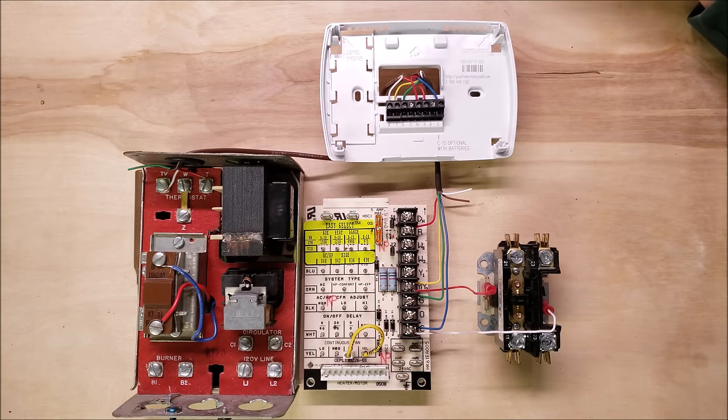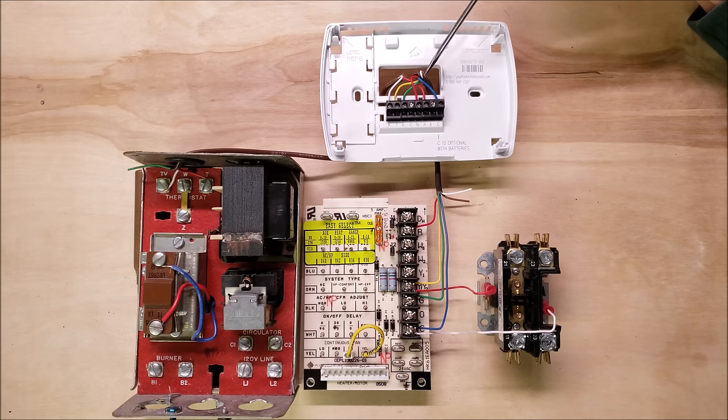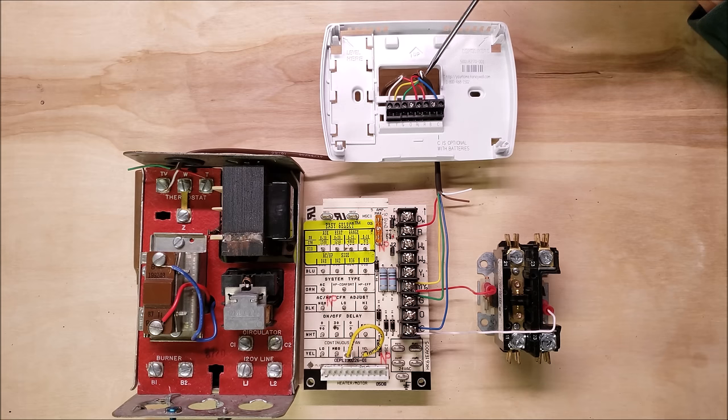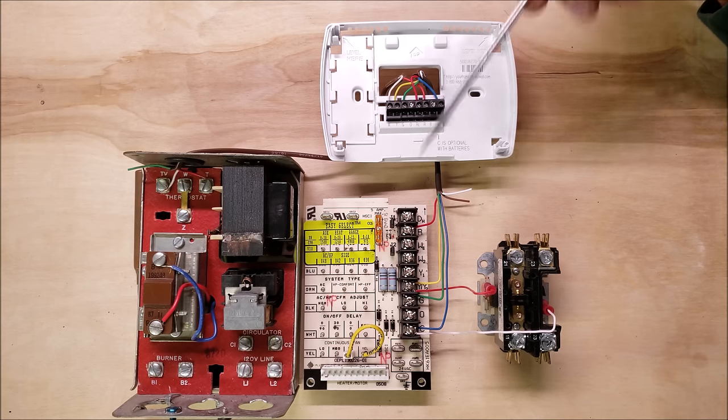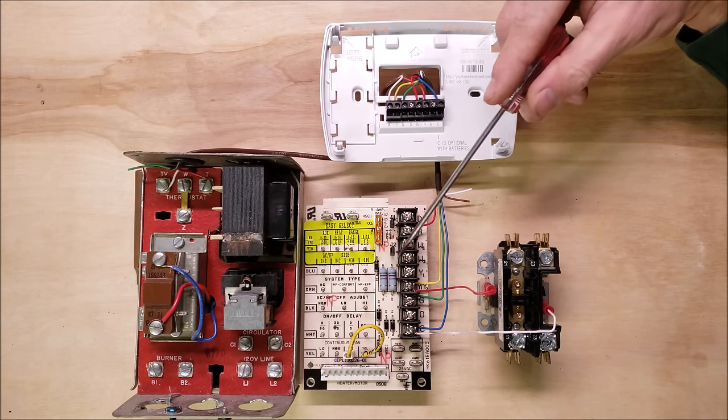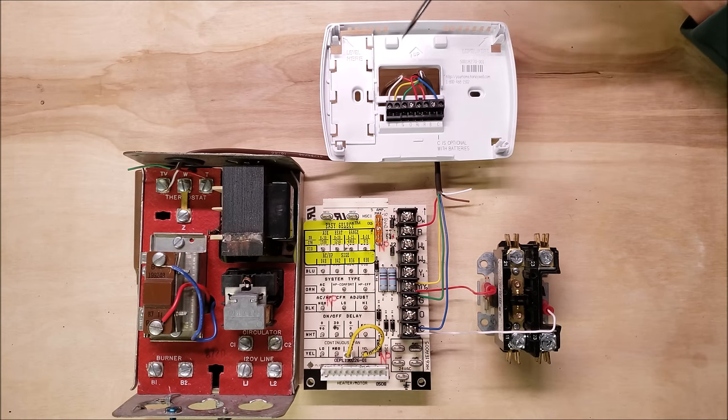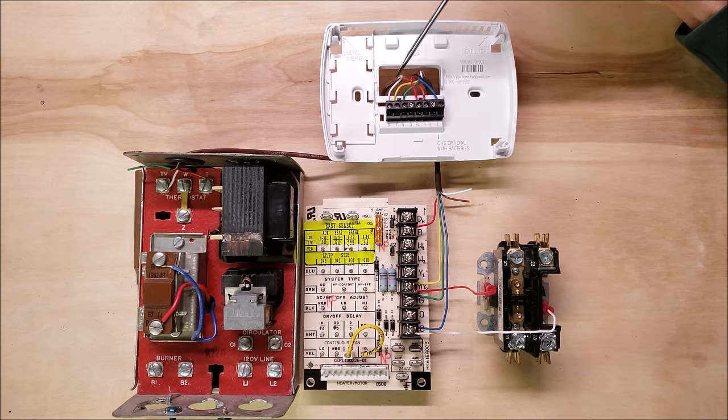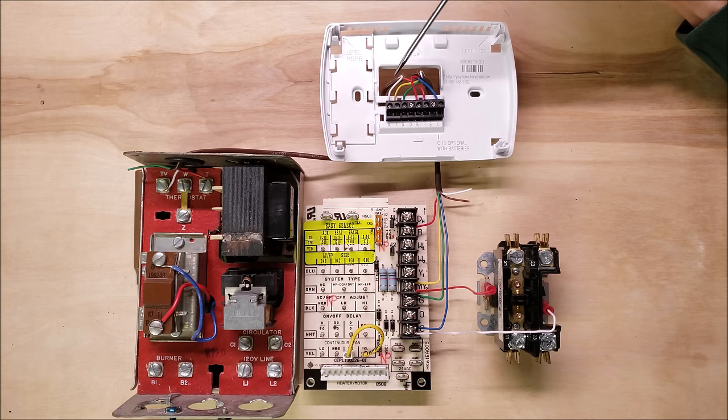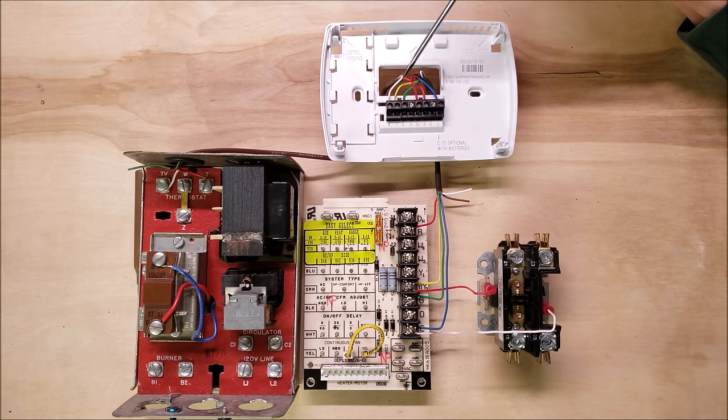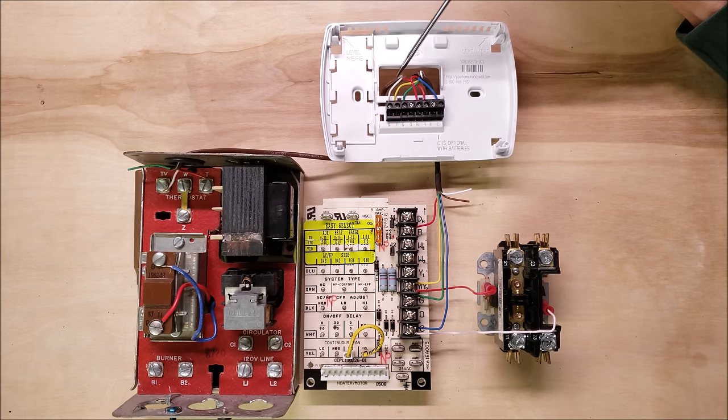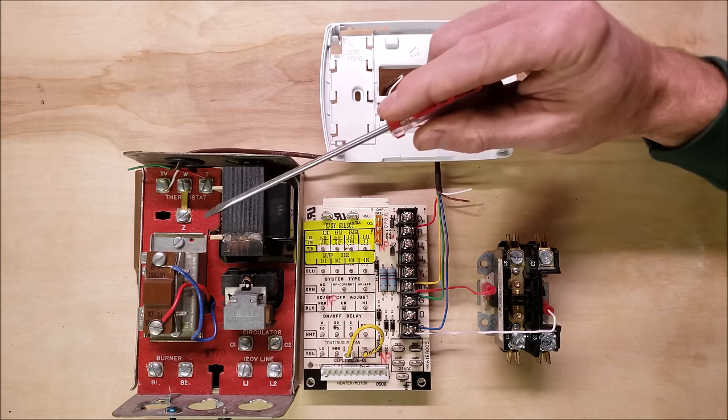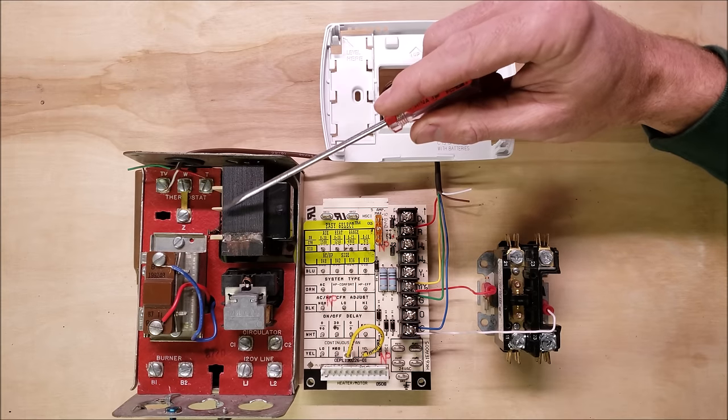Coming out of the thermostat we have two sets of wires. Right here is an 18-6 wire but we're only using four of the six wires heading to our indoor air handler. Then you have an 18-3 wire and you're using two wires out of that. This two wire is actually heading over to your Aquastat controller.